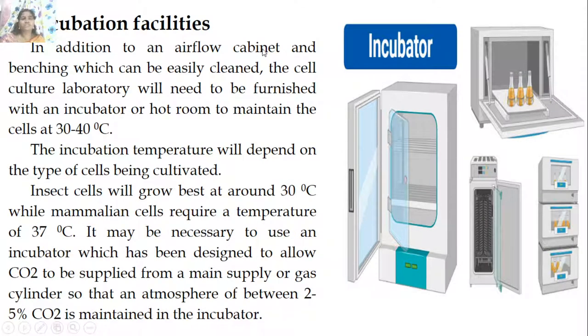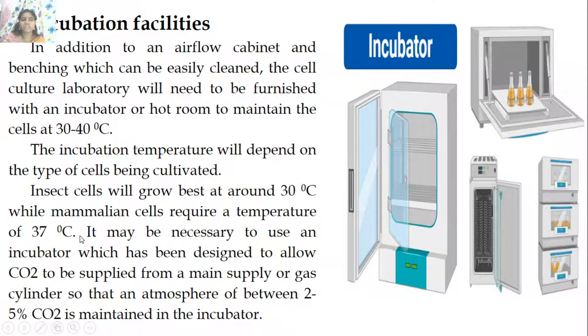Incubation facilities: in addition to the airflow cabinet and benching, the cell culture laboratory will need an incubator or hot room for maintaining cells at 30 to 40 degrees centigrade for growth. Insect cells grow best at around 30 degrees while mammalian cells require 37 degrees. It may be necessary to use an incubator designated to allow carbon dioxide from a gas cylinder so that an atmosphere of 2 to 5 percent CO2 is maintained.